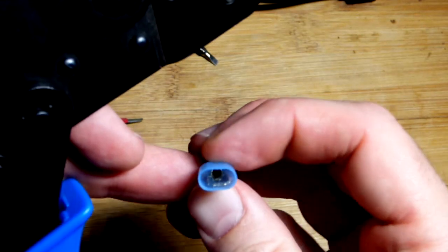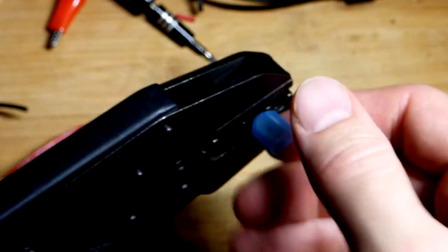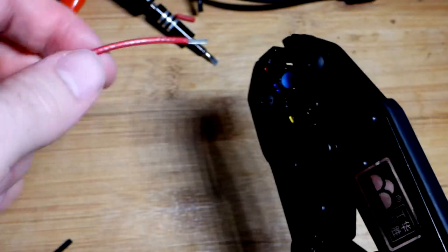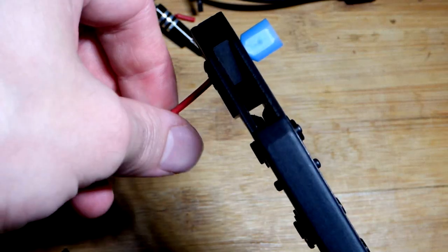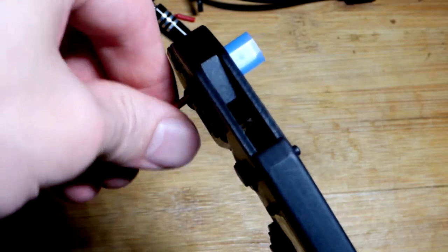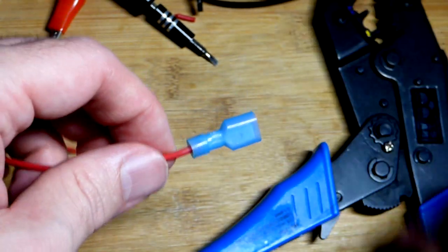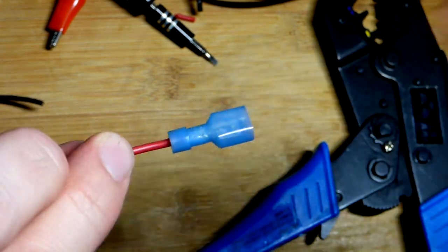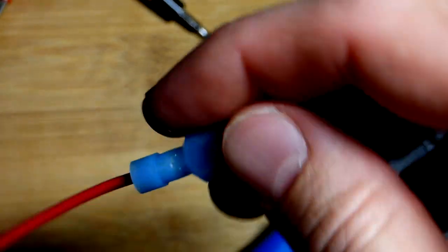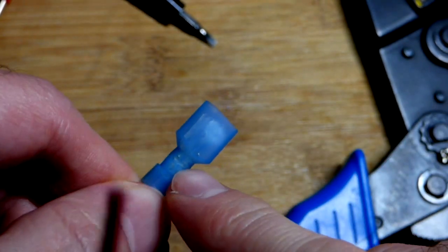So now we got the connector, we're going to put it in upside down. Remember the blue one was the middle one, and we're going to close it down. It doesn't really matter which way the wire is going here. I believe that's twisting it the same way I twisted before. I'm going to insert it all the way in. Squeeze her down, release her, and should have a good grip on the wire. I'm pulling on that fairly hard. This particular one I don't think will have the two dimples. Oh it does, you may not be able to see it, but it actually has the two dimples, which is a sign of a good connection.